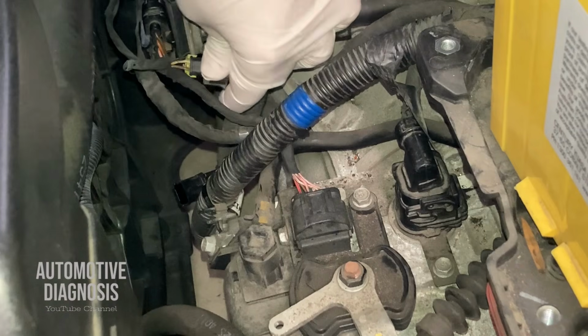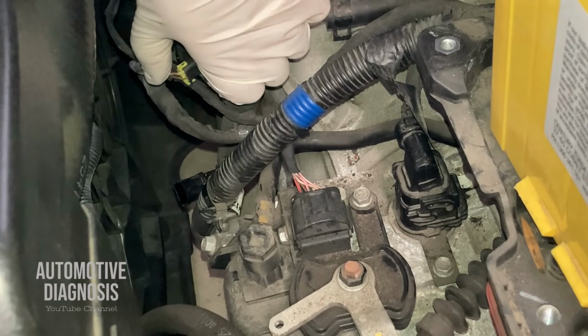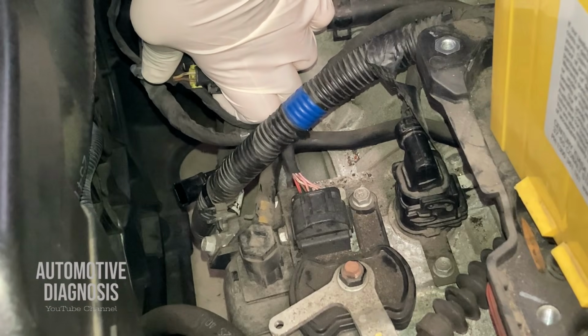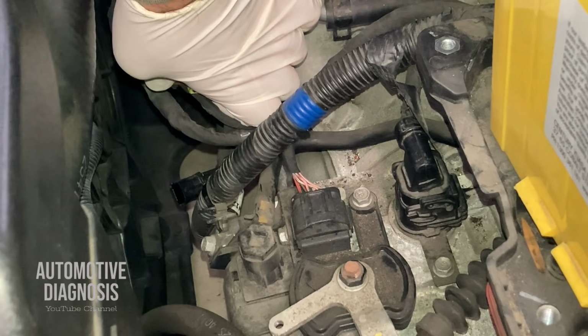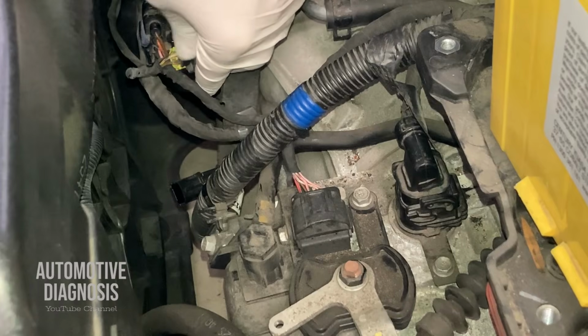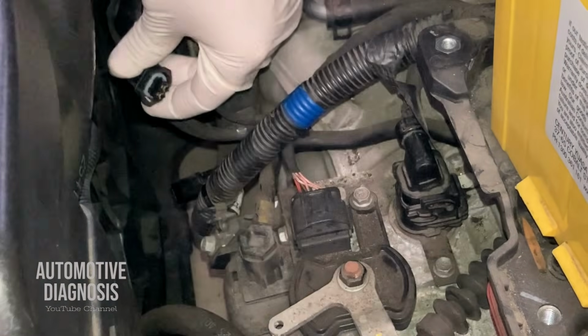As you see, we have 2 wires, as I explained earlier on the wiring diagram, brown and white wire. Brown is the signal, white is the ground. I'm going to back probe each one of them - you can just test it from the front side as well.